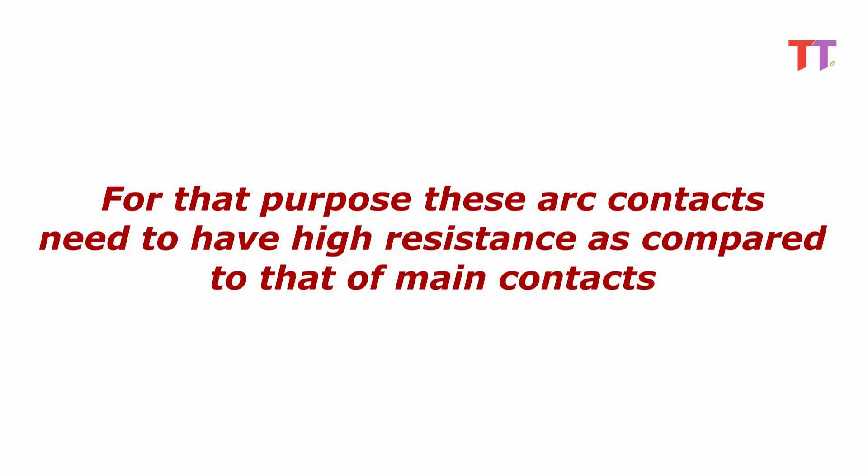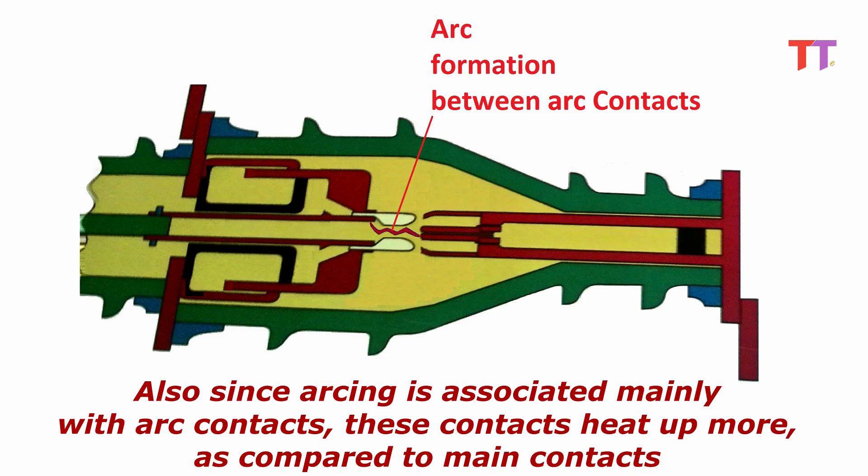For that purpose these arc contacts need to have high resistance as compared to that of main contacts. Also since arcing is associated mainly with arc contacts, these contacts heat up more, as compared to main contacts.